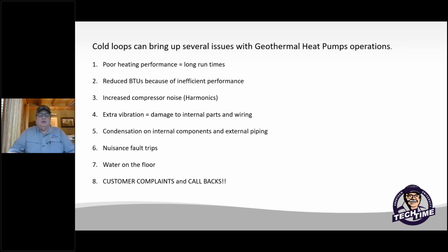It also reduces the BTUs. As we know, the colder the loop field is, the less efficient it is, and the fewer BTUs are available for the homeowner. You'll also find we've heard of problems with compressor noises and the harmonics associated with colder loops.